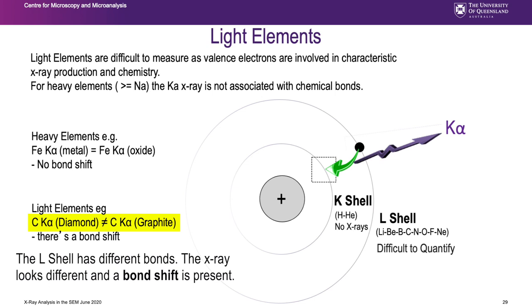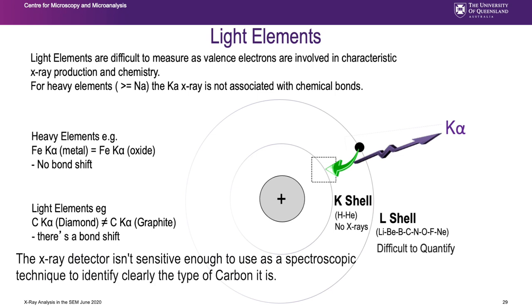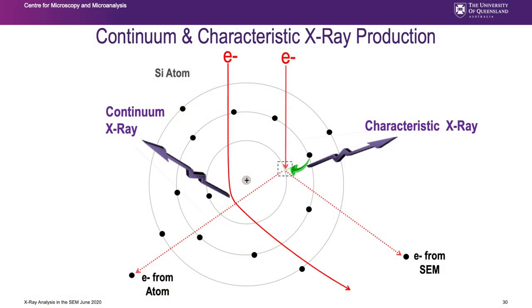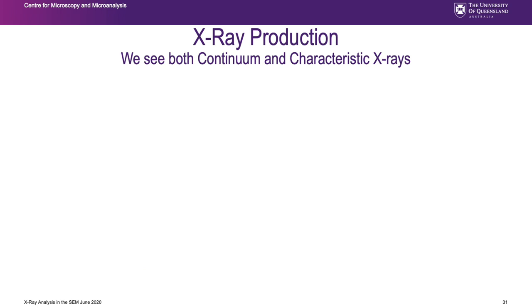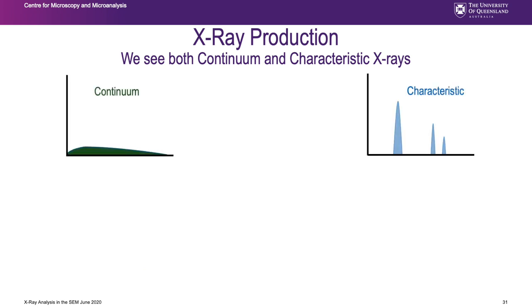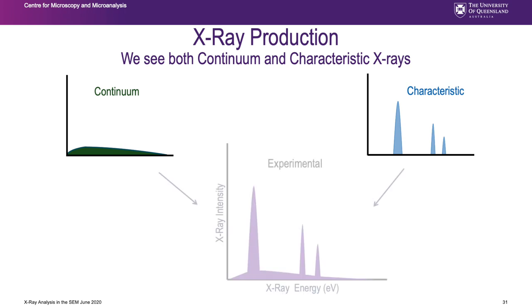This bond shift is difficult to measure - my X-ray detector is not sensitive enough to use it clearly as a spectroscopic technique, yet it's enough to make the measurement difficult without being useful. So light elements are very hard to measure. When the primary beam hits your specimen, both effects happen simultaneously: characteristic X-rays and continuum X-rays are produced together. That combined result is what we actually see with our detector in experimental data.